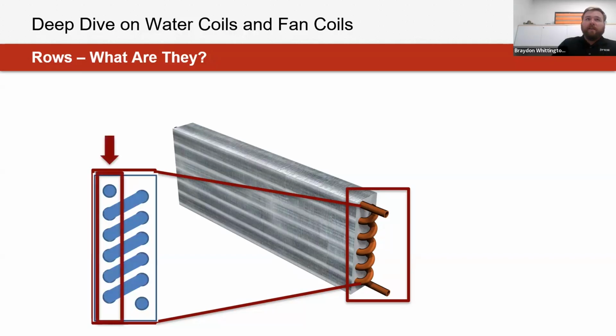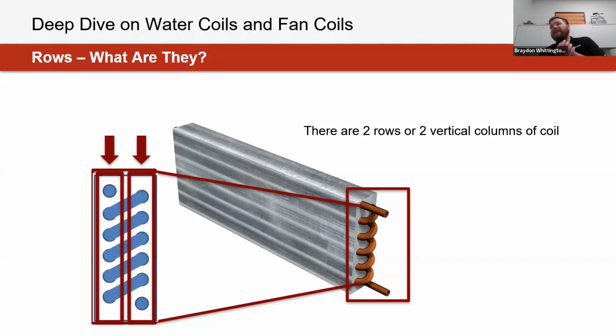That's awesome. It's a little bit harder to see based off of the ISO view of this, but this is actually a 2-row coil. And how do we determine that? Well, it's going to be the amount of vertical columns that is actually on the coil itself. Commonly, especially with these helical flow or tighter 1 or 2-row coils in the industry, you might misinterpret, based off of having just one entry point and one leaving point, that it's a 1-row coil. But it's actually the amount of columns going through the coil itself. So in this case, this one is a 2-row coil.